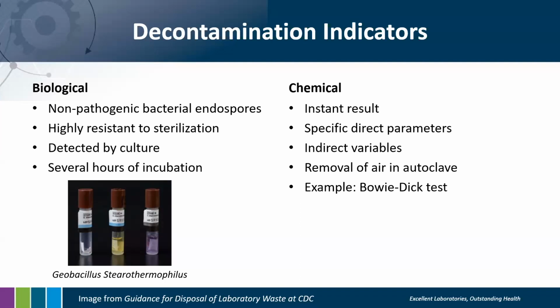In this type of indicator, when used, for instance, in an autoclave, say you were validating your waste disposal procedure and you want to use this indicator: if the sterilization process is not effective, spores will germinate, grow, and release an acid that can be detected by a pH indicator dye present in the growth medium. This figure shows this biological indicator, or BI, tubes. You can see an unused vial that was not autoclaved on the left of the figure, and a failure control vial that changed from purple color to yellow after the spores grew. That's in the center of the picture.